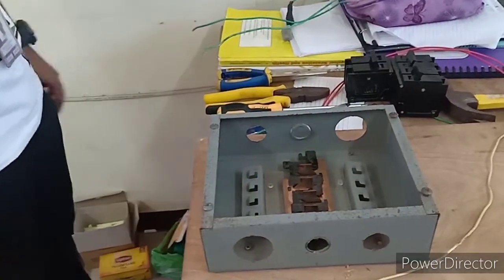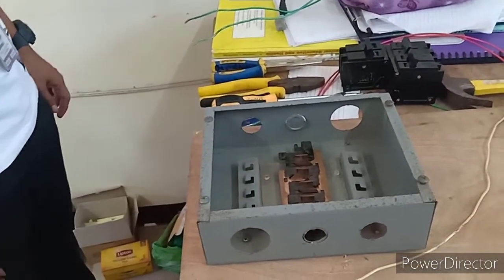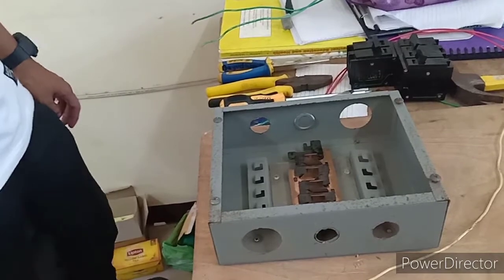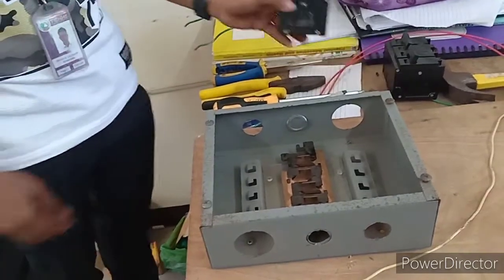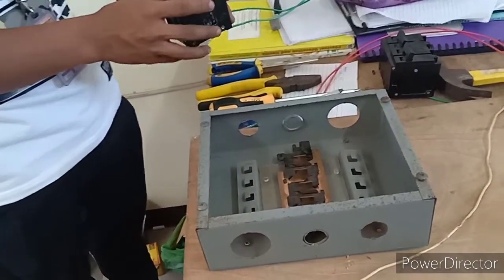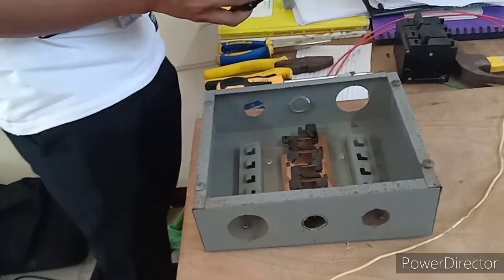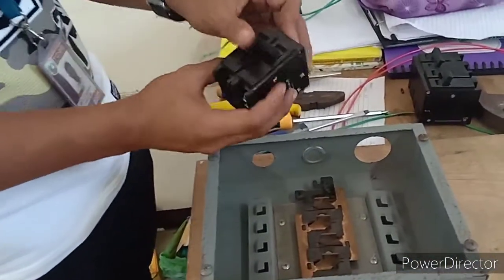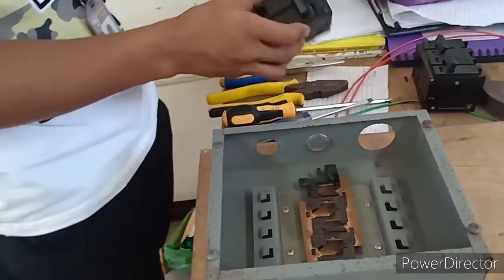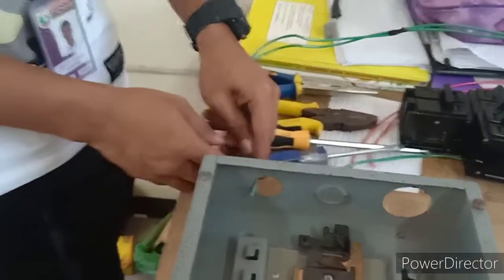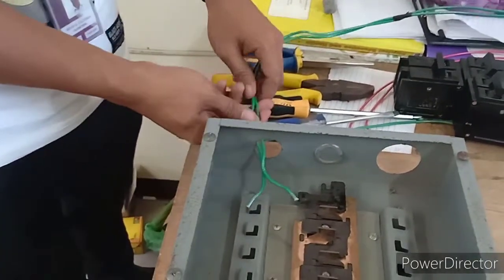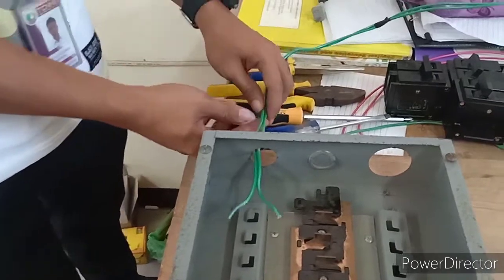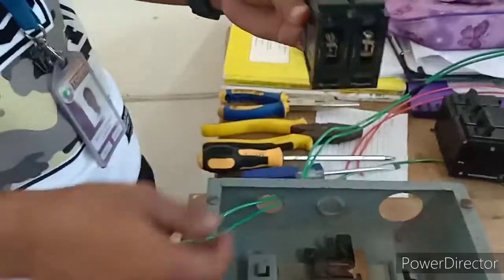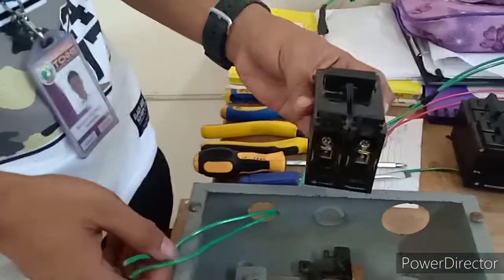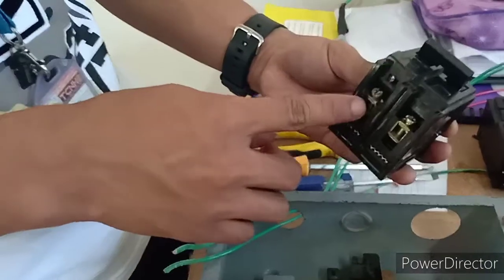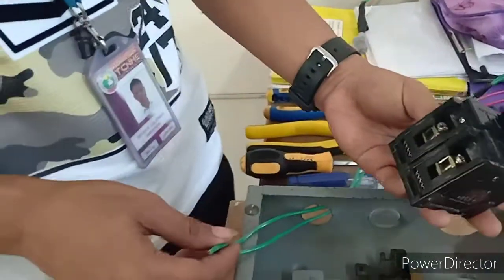After you install the panel board, be sure to have your main breaker that is computed according to the need of the supply of building or the appliances. So put the service entrance wire that is number 8 to the terminals of the circuit breaker. Terminals of a circuit breaker, line 1 and line 2.